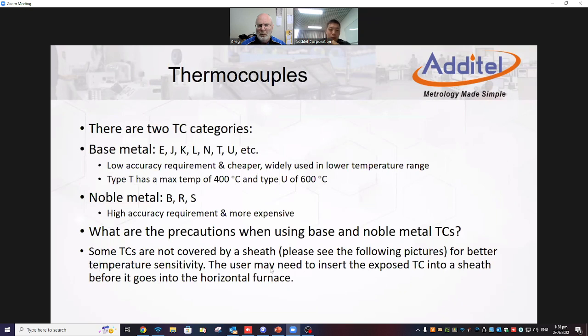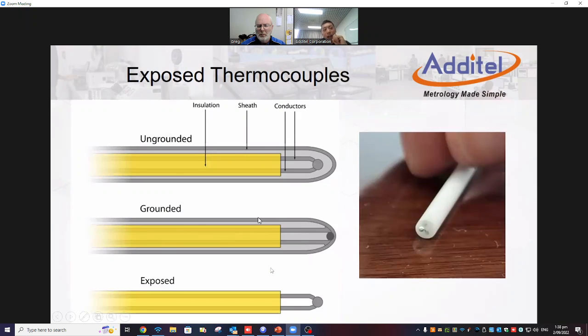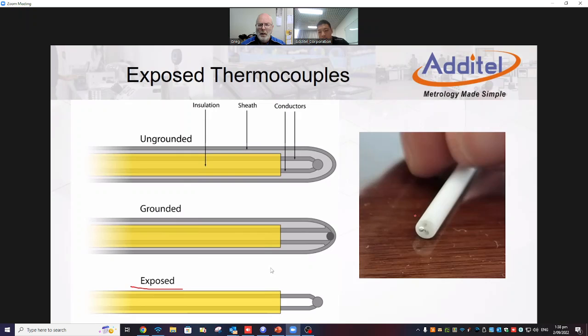So for the base metal thermocouple, especially with the shell, we don't need to worry about contamination. But for noble metal, S and R, I would say 80% of the noble metal probes we have are exposed thermocouples, like the picture below, like this one. The problem with this one is you can see the thermocouple tip is actually exposed to the environment.